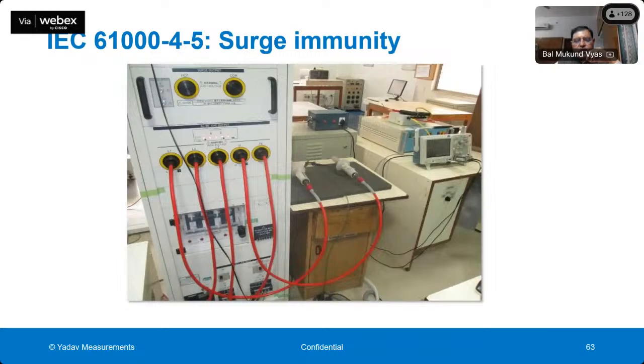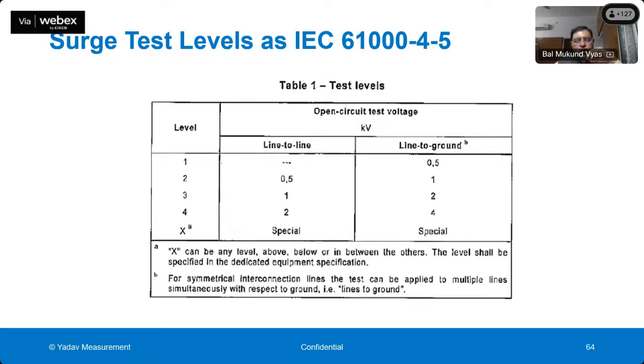This is a typical lightning surge test setup. This is a lightning surge generator, which can generate surges up to 15 kV, and the meter has to pass these tests as per IEC 61000-4-5. Typically a 4 kV surge is specified. In the Indian standard it is 6 kV, but what we have seen is that in areas like Odisha or coastal areas like Mumbai, the surge level is very high. So my recommendation is to test the meters to a surge level of at least 10 kV to ensure that they work very reliably in the field.